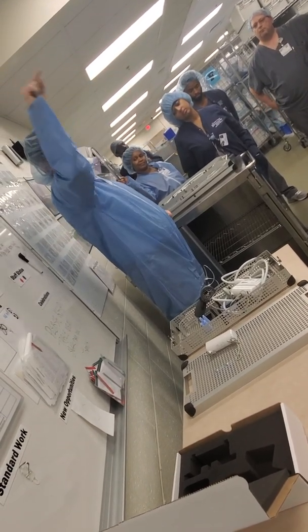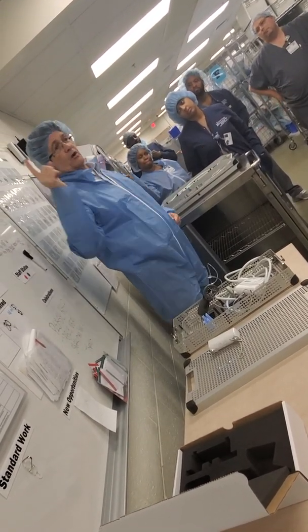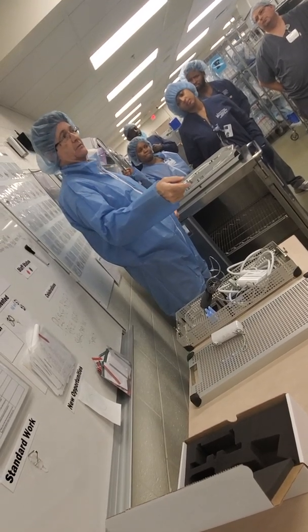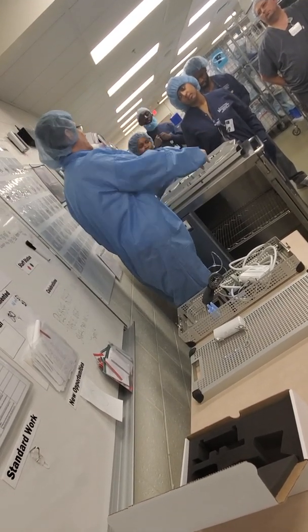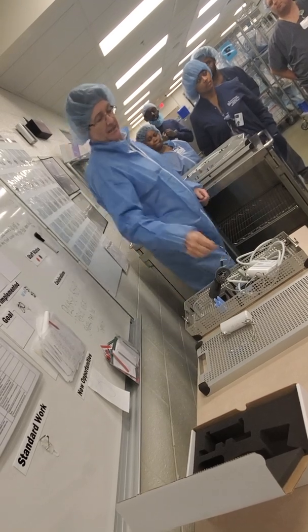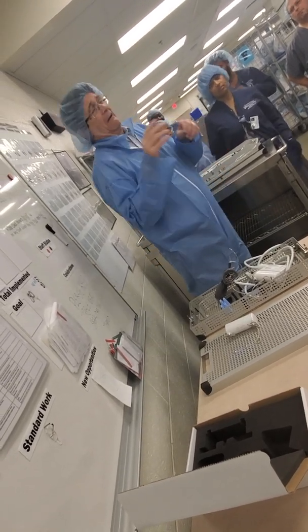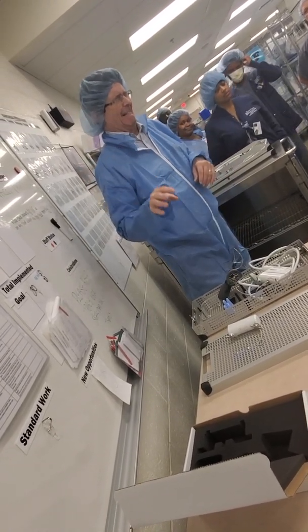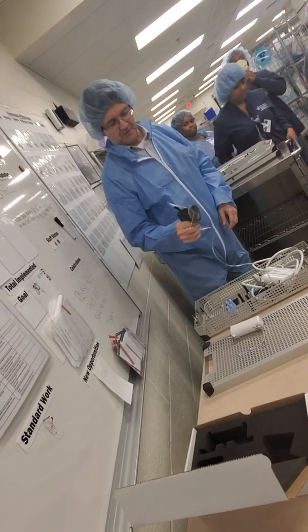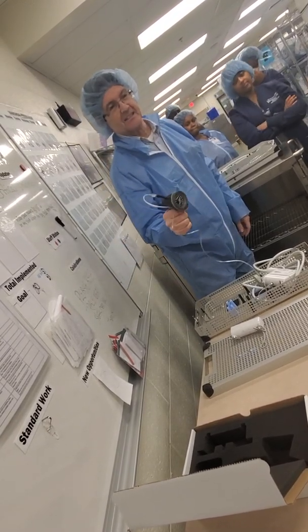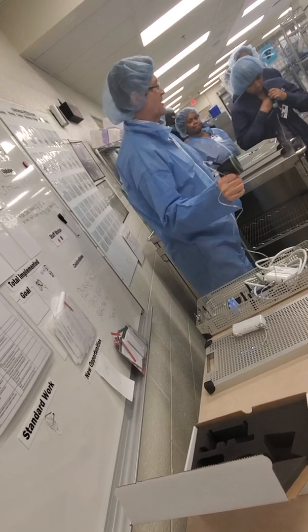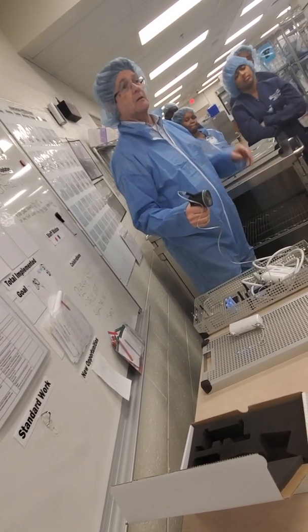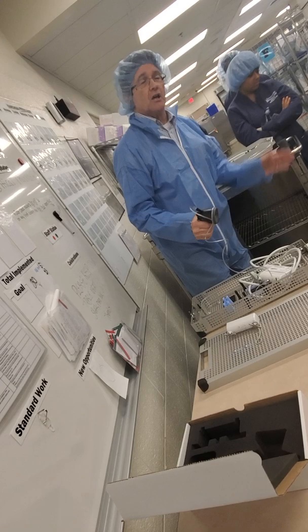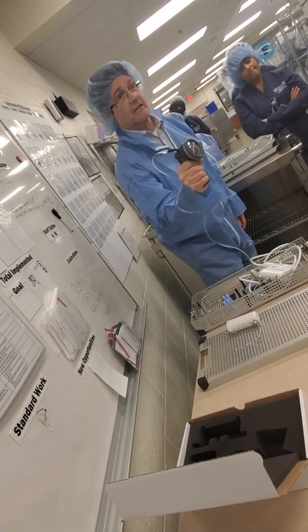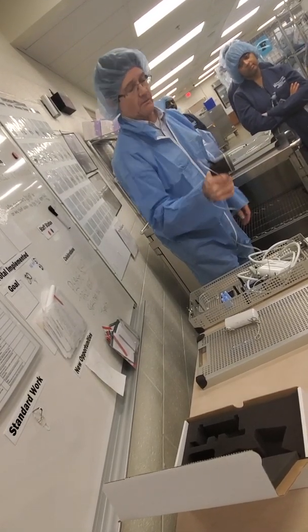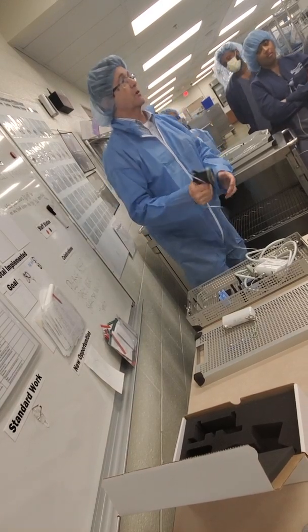If it goes into water like that, that probe costs $25,000. Not repairable. So if you don't see it, and it does this, say, wow, something's wrong. Then you look and say, uh-oh, put it aside, don't put it in the water. Don't put it in the water to finish the test, because you can't, right?